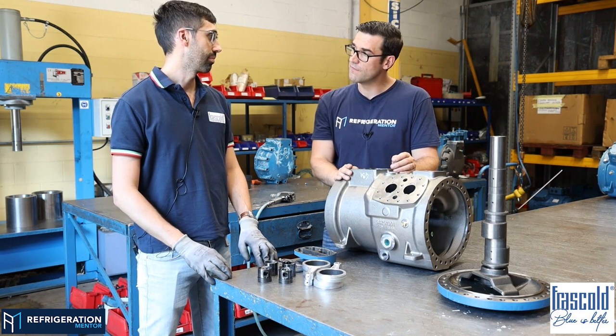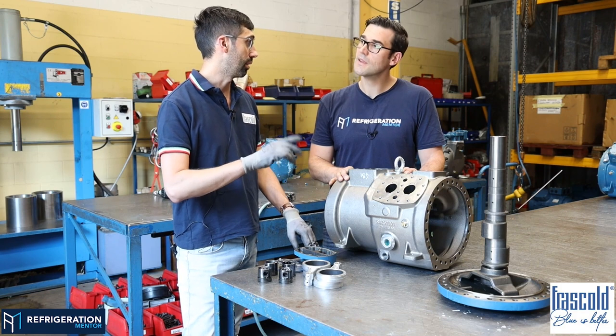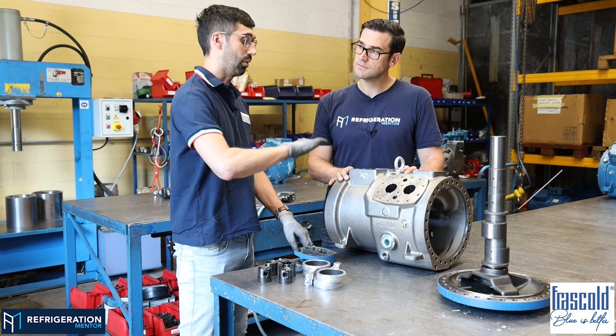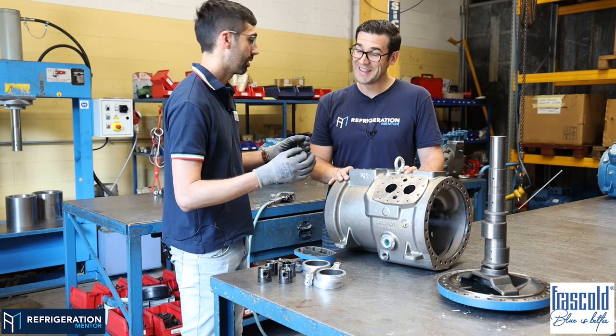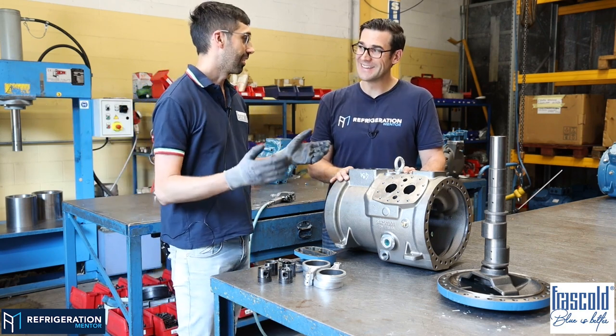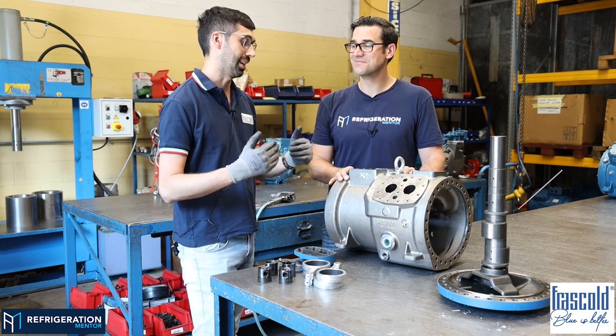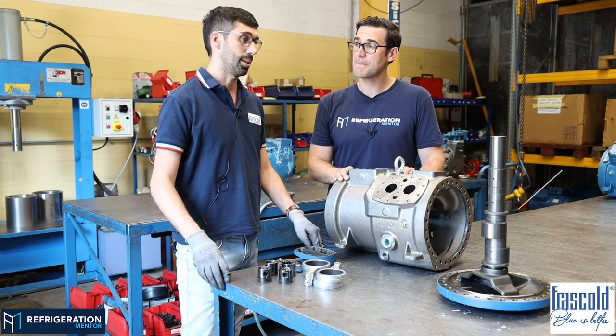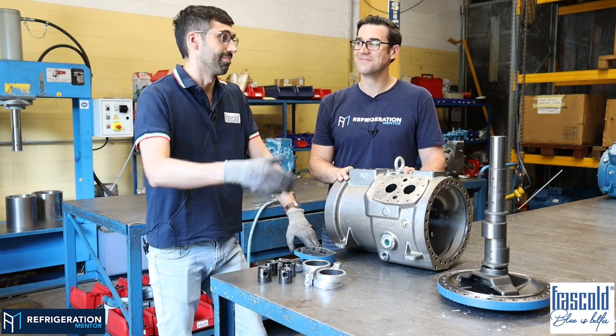What are a few other electrical failures that could happen? Sometimes the stator can be connected for 400 volts or 230. But technicians that make the installation must know how to mount the jumpers. Because sometimes a brand new compressor comes back. What happened? Oh, I forgot to change the configuration of my jumpers, and I immediately burned out my motor. So it is a procedure error on the commissioning that in some cases happens.